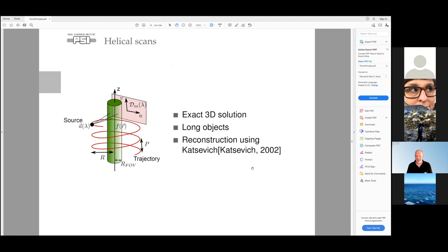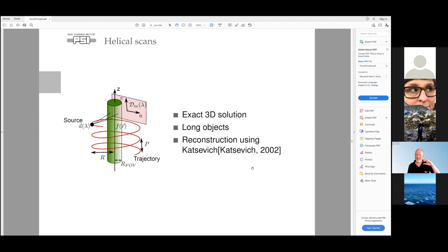Another way to handle cone beam is to use a helical scan: while rotating the sample, you're also translating it vertically, which gives an exact solution without Feldkamp artifacts. This is a very good method for X-rays where there is some beam divergence. With neutron imaging, I don't think anyone has tried it because the pitch would be so small it's hard to motivate. But with X-rays it makes a lot of sense — it's the technique used in modern medical scanners because you get much better reconstruction quality.